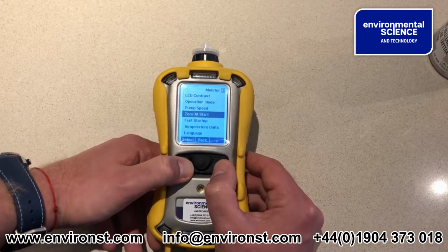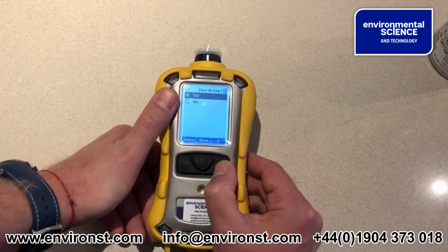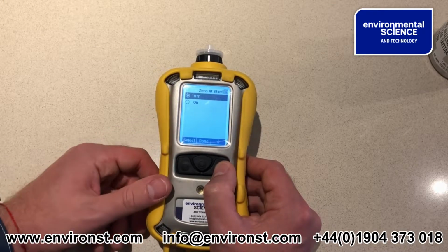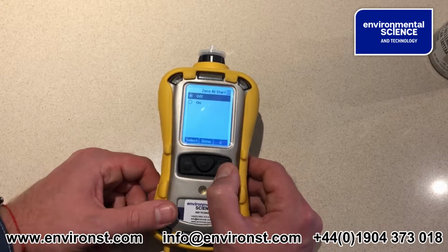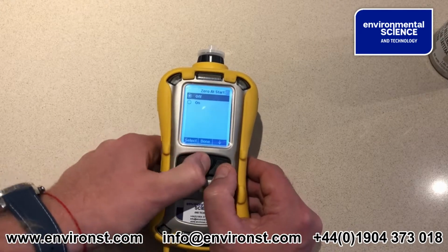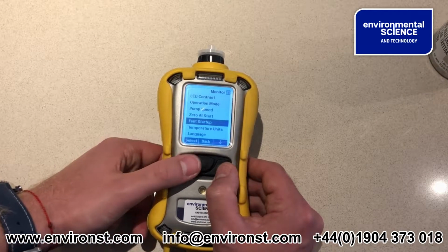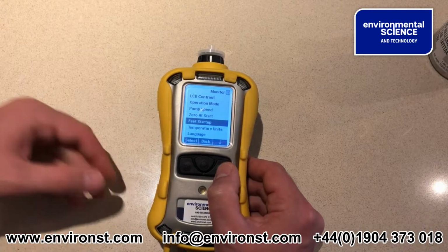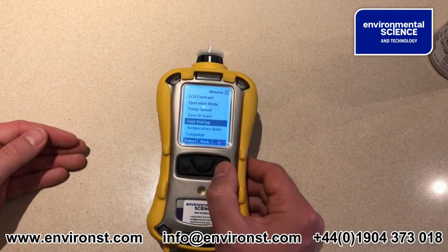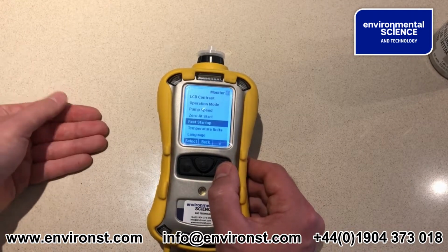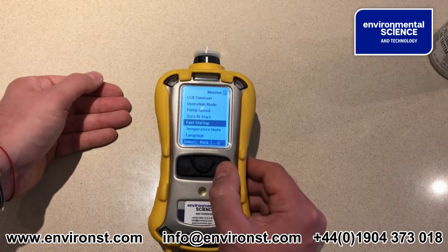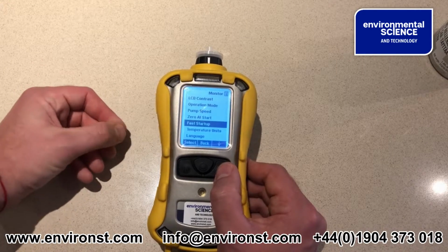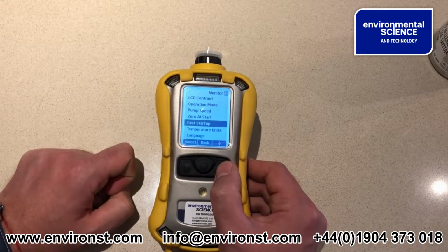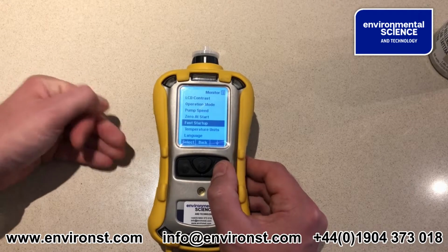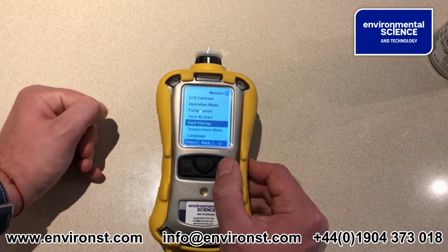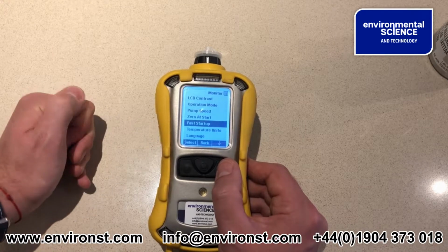Zero at startup. Now some people have this turned on, some people have it turned off. This is essentially exactly what it says. It will zero the sensors when the unit starts up. Fast startup. This is essentially where it doesn't go through all those scrolling menus of each of the sensors, telling you its calibration dates and everything like that when it starts, and tries to go as quickly as possible to readings. Now, as we originally said, these sensors need time to warm up regardless. So personally, I see no point in this function.